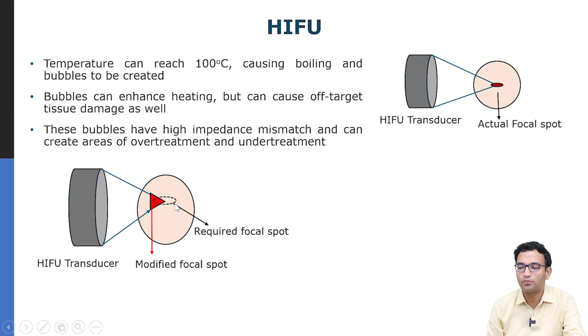Now, these bubbles also have an effect of shielding the target. So, let us assume that you would like to destroy this region. Assume that some bubbles are formed here. These bubbles have a high impedance mismatch, and they will also reflect the sound to a large extent. So, they will modify the ultrasound beam and they will shift the focus, because of which sometimes the distal regions are not properly ablated and you get asymmetric lesions.